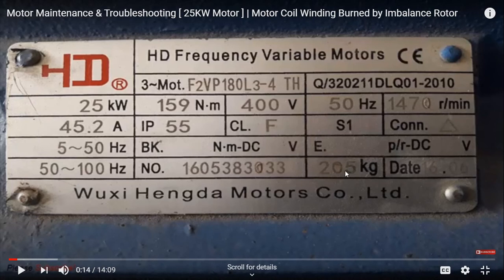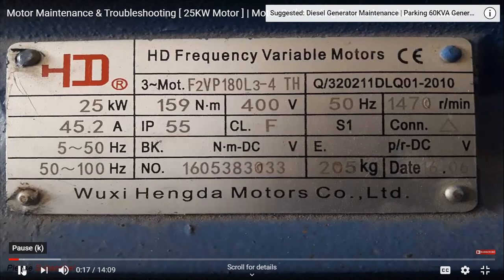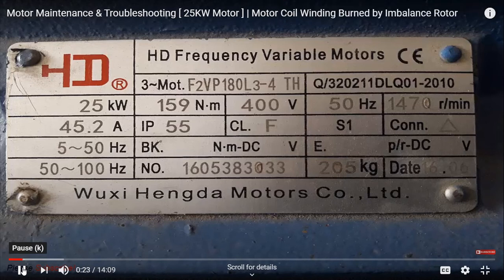These details are particularly essential while you go for maintenance. Keep a record of that and note down which company made this motor. It runs at 1470 RPM, its ampere rating is 45.2 amps, IP rating is 55, and it's a delta connection motor.